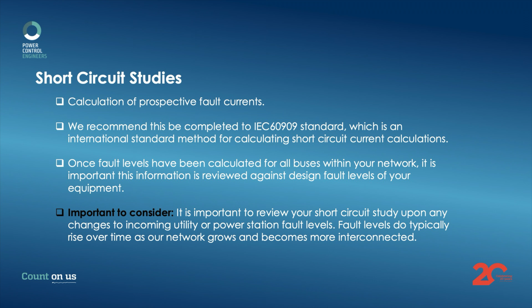One important thing to consider is that it's important to review your short circuit study upon any changes to incoming utility or arrangement fault levels or power station fault levels. Fault levels do typically rise or go down over time based on changes in the network, and these do make a profound impact on your power system model, particularly the short circuit study.